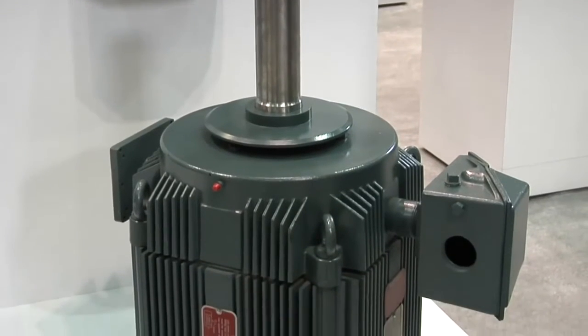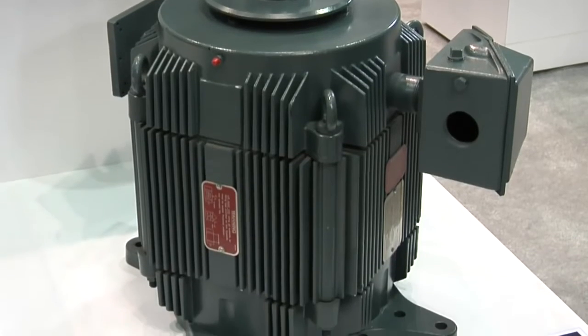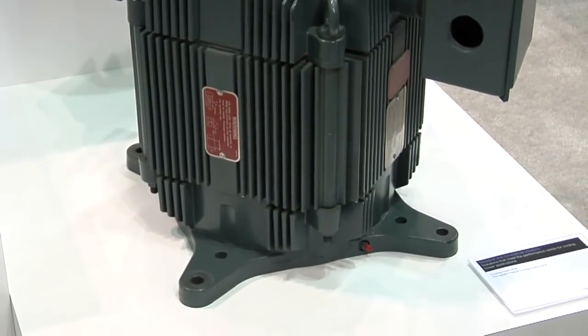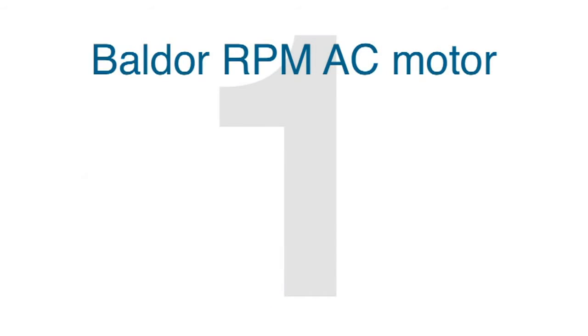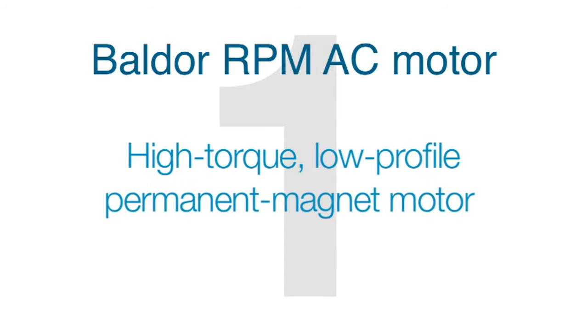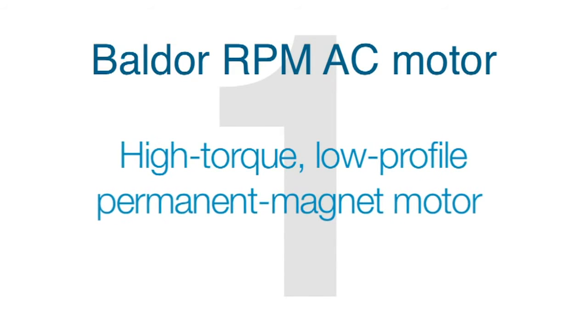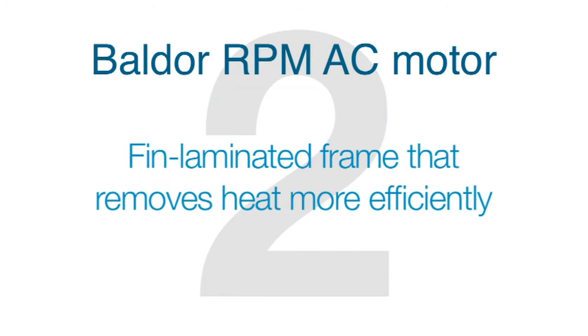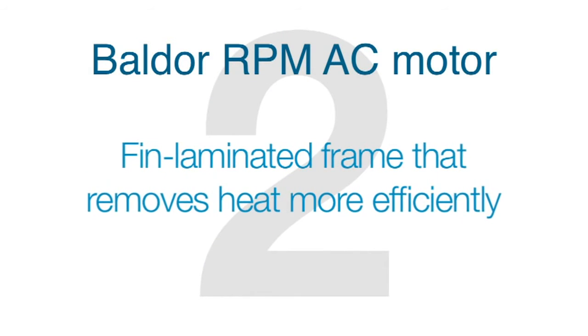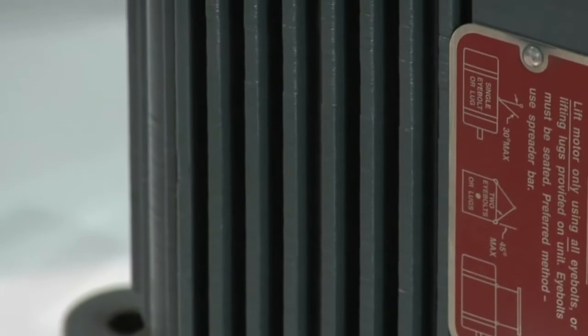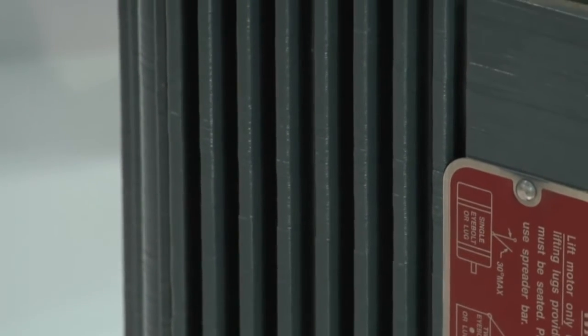The Baldor solution is an RPM AC motor. It's a vertical motor that is really something special, with 4 features that adapt it perfectly for cooling tower fans. First, it's a high torque, low profile permanent magnet motor that has 0 slip and is much more efficient than NEMA motors. Second, the stator body is a fin-laminated frame that removes heat more efficiently and results in a smaller, more power dense motor.